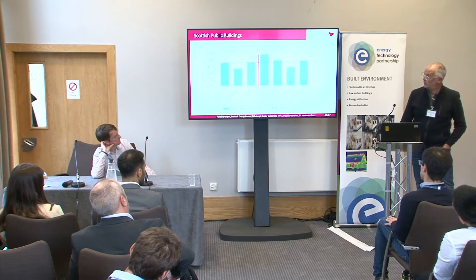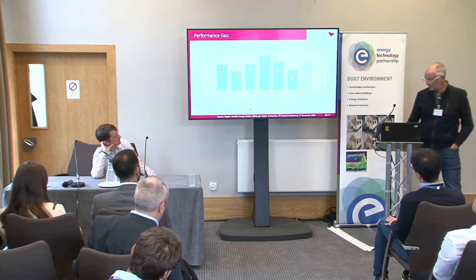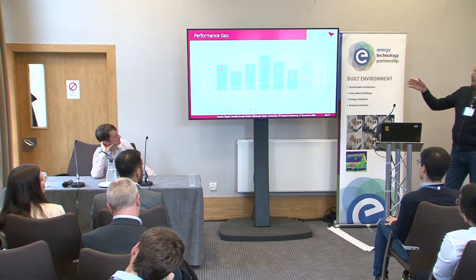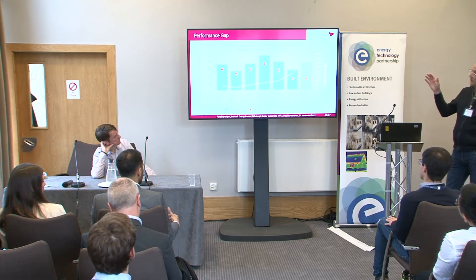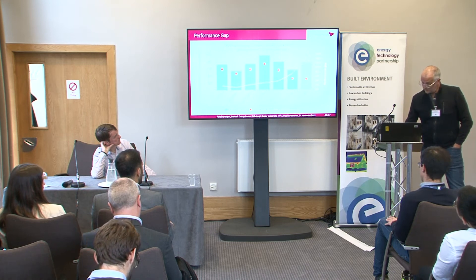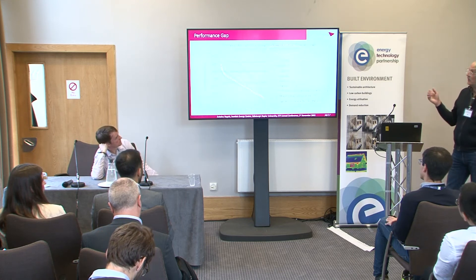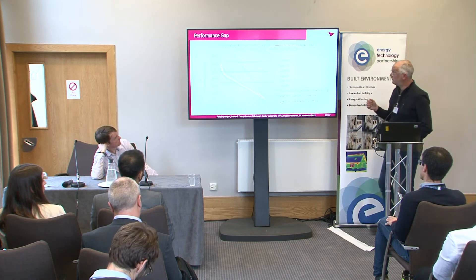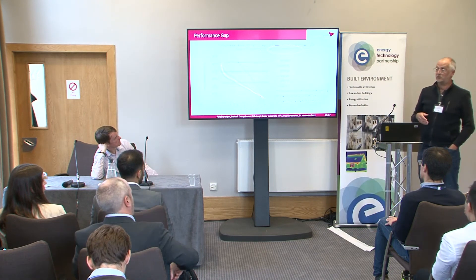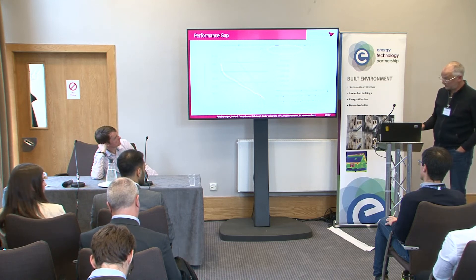Comparing the calculated EPC to actual true energy use, we have a performance gap which is increasing across age groups. Applying that performance gap to the flow temperature you could apply in heating systems, the most recent buildings are eventually less likely to be able to use low temperature heat, while older ones are still able to use it because their performance gap is more reduced.